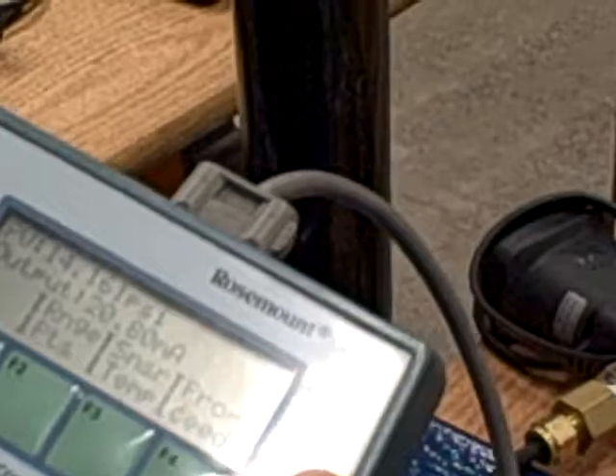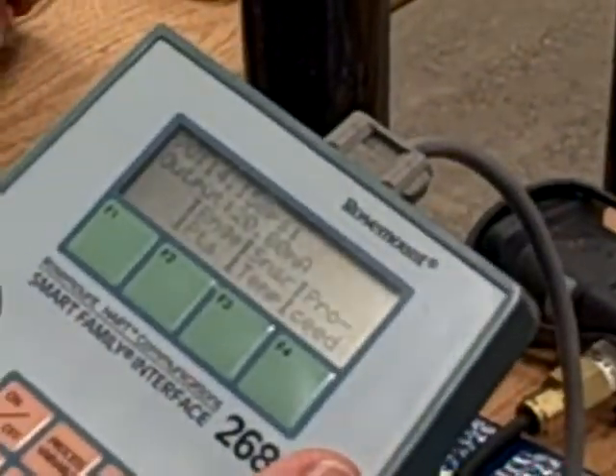So according to the Fluke, how much pressure do we have? 14.14. 14.14. And according to this, we have 14.16. That's a very small percentage error. I'm comfortable with that. I'm going to turn it down even more.